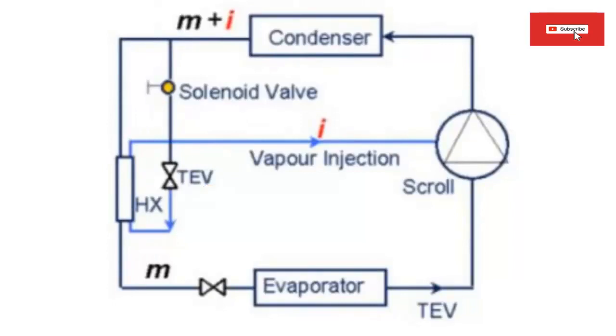30. A solenoid valve should be installed in the liquid line, which feeds the economizer, in order to prevent migration of the refrigerant liquid to the compressor when the compressor stops.